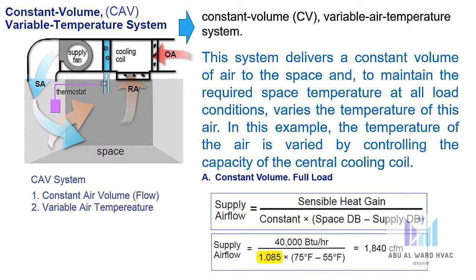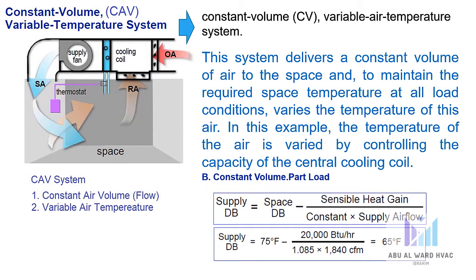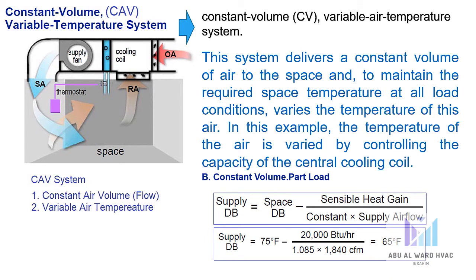In the full load condition, if we calculate the supply air according to the formula — sensible heat gain divided by a constant multiplied by Delta T — with a supply air temperature of 55°F, we get a supply air flow of 1,840 CFM. In the part load condition, we calculate the new supply air temperature according to demand. If the total sensible heat gain is 40,000 BTU at full load and drops to 20,000 BTU at part load, substituting into the formula gives a supply dry-bulb temperature that increases from 55°F to 65°F.